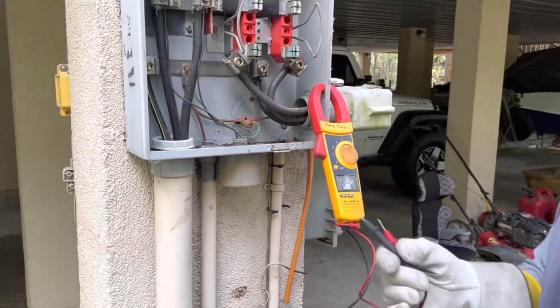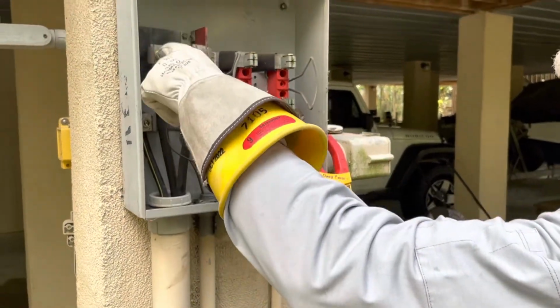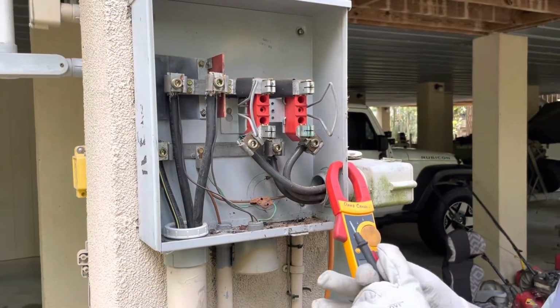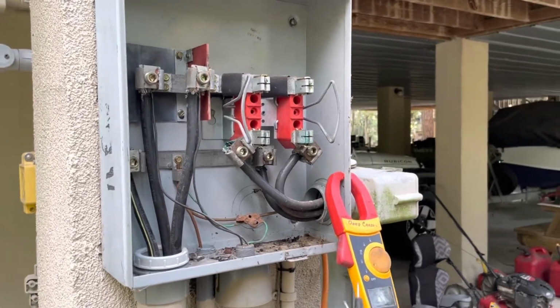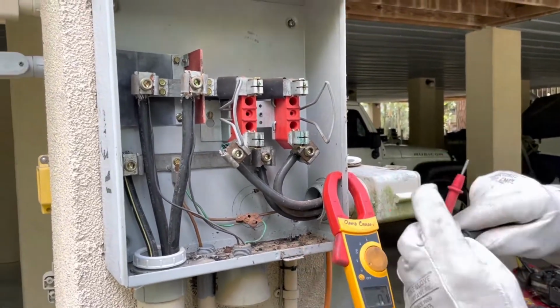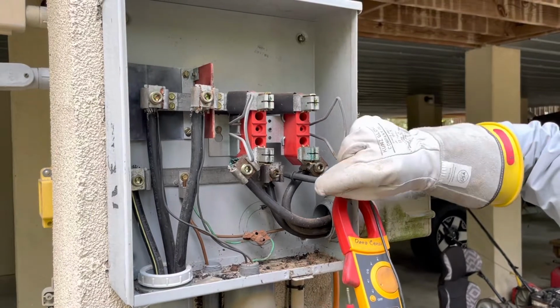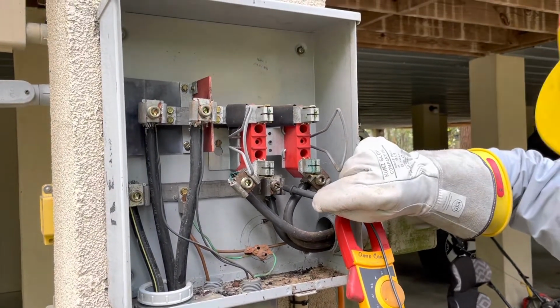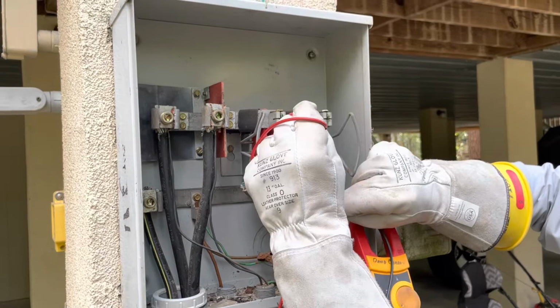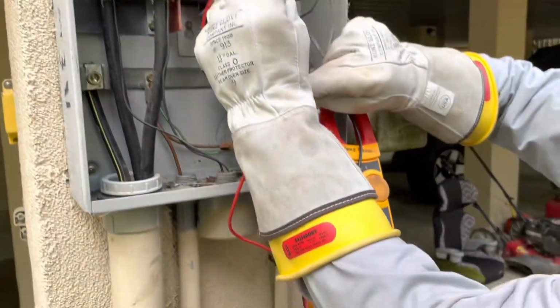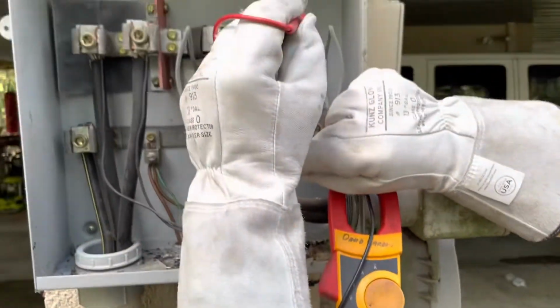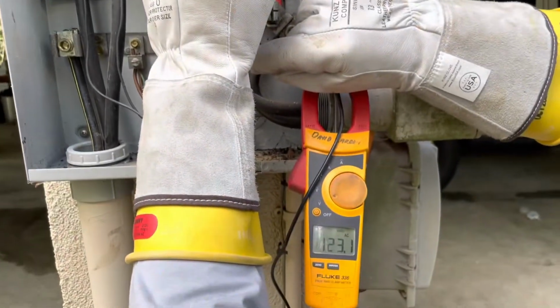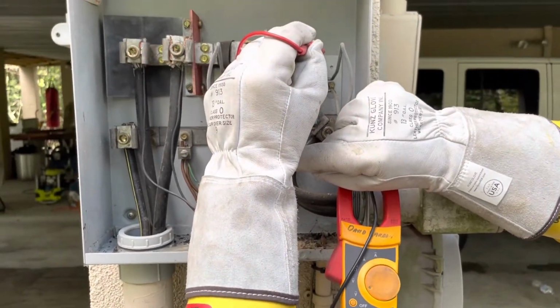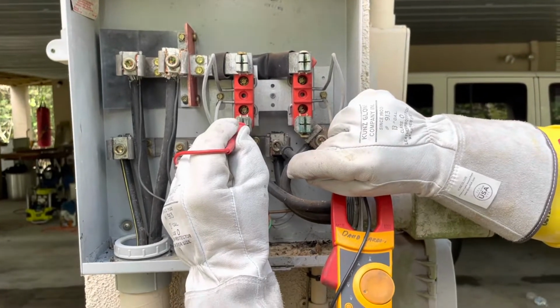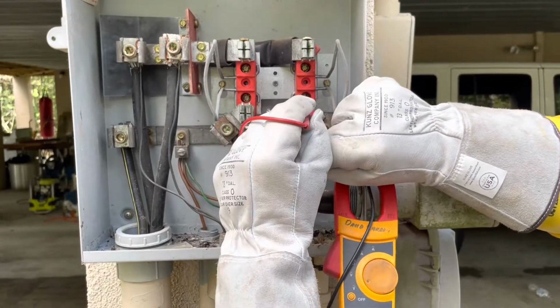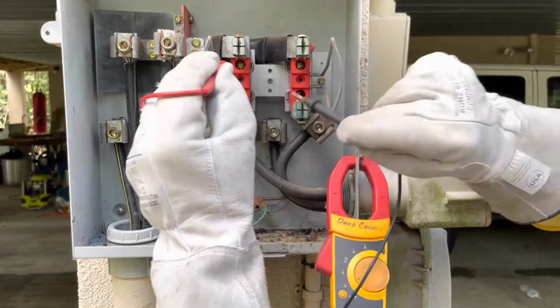As you can see, this is the underground service that comes in, and it goes over to these bars on the top. So what we're going to do is take our leads and go to ground. This is the ground. And we're going to go top left lug. I get 123 volts. Top right, I get 123 volts. Bottom, nothing. Bottom, nothing. And let's go phase to phase.